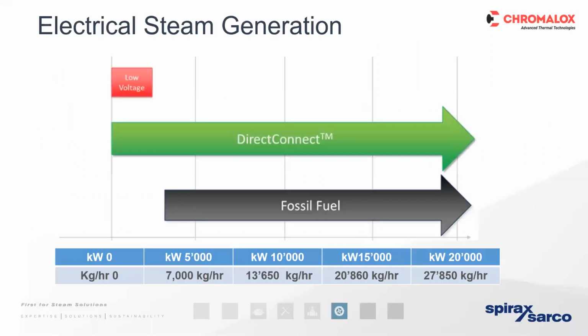And a medium voltage system, that's an ideal solution for applications that are greater than 879 kilowatts. That's around about 1,600 kilograms per hour, which is relatively small by traditional steam boiler standards. So it's really just a question of ensuring that the appropriate direct connect, that's the trademark, electrical heater is selected to match the required steam mass output of the process.